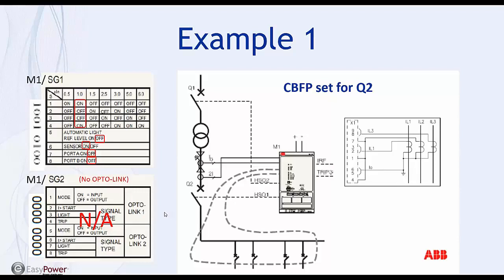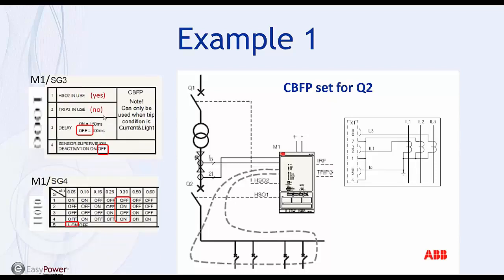Now for setting group 3, that's the breaker failure. We're going to use breaker failure, so it's important to have the current and light switch in the current light position. We're going to use high-speed output 2 for breaker failure. We're going to set it at 100 milliseconds, and we're going to supervise the loop. For the ground, we're setting that to about a third with the dip switches, and then switch 5 has to be on to let the unit know that we're also measuring and using ground fault current.